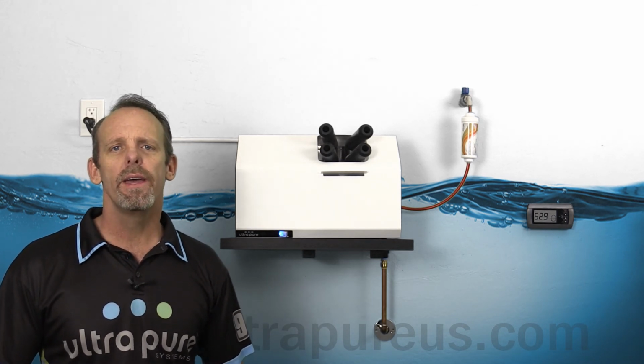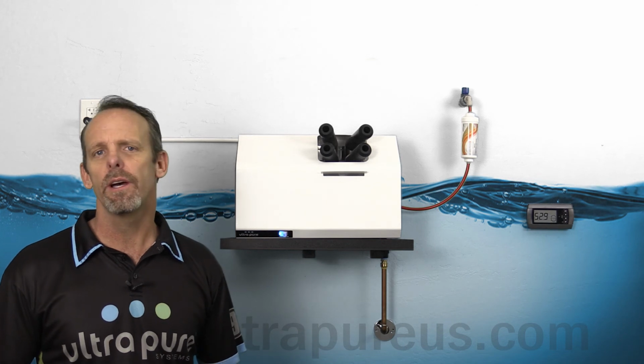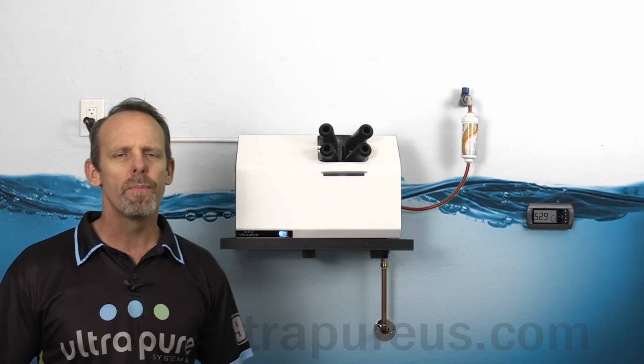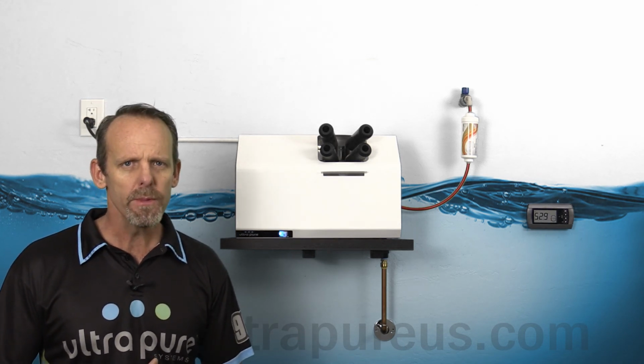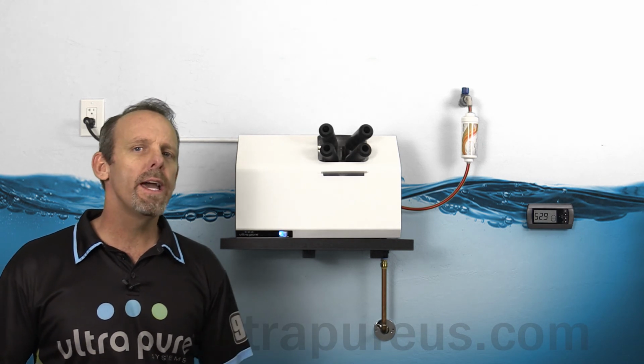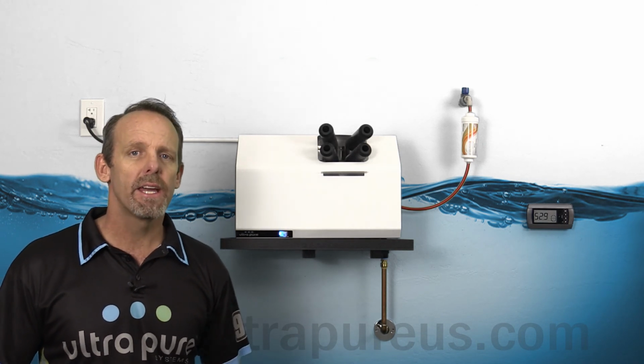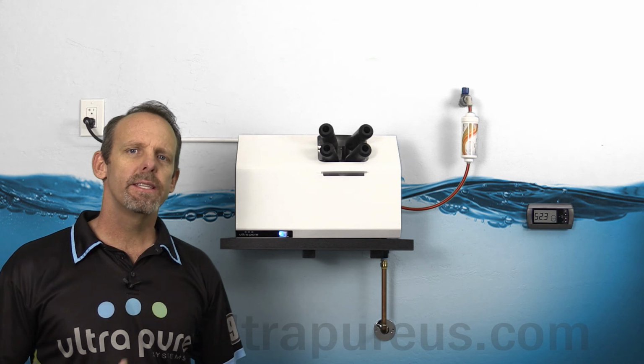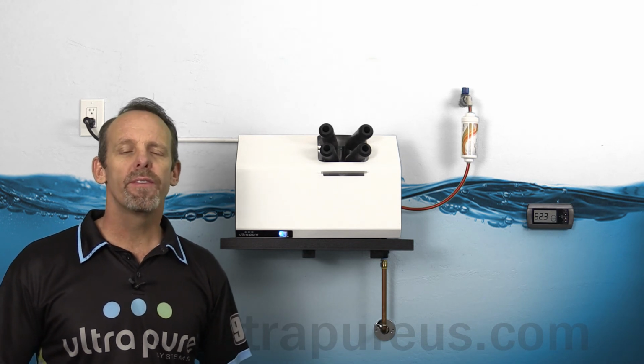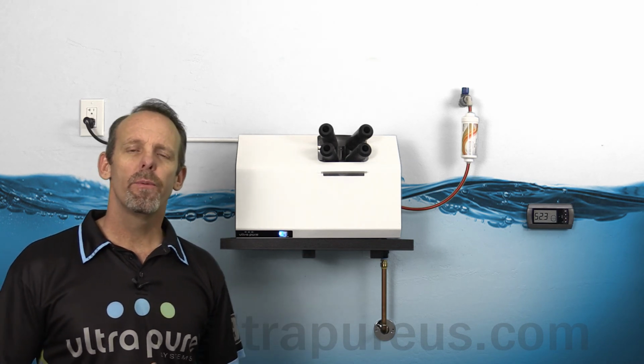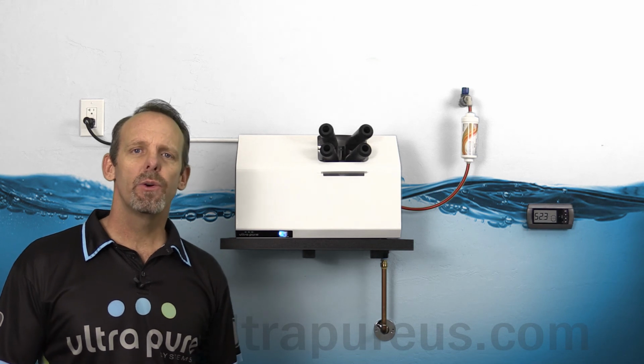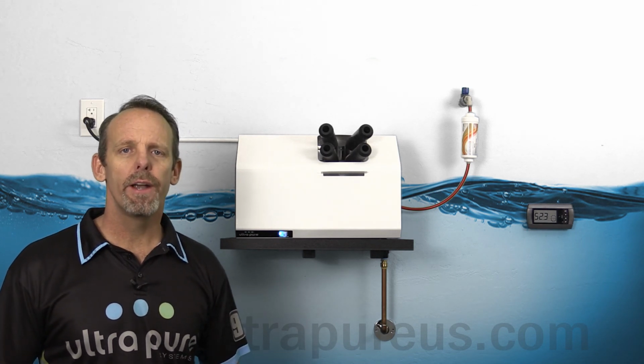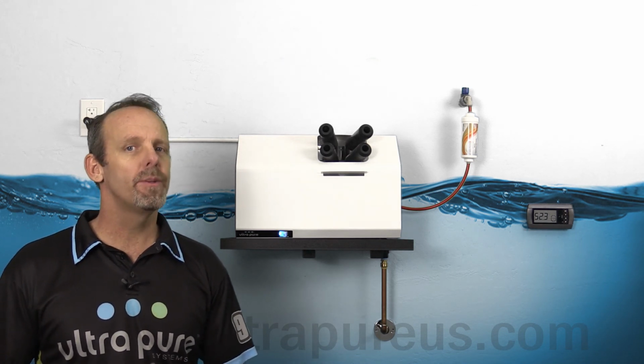We also have a switch. It's actually a current transmitter switch, very small, hooks up to our humidifier, and you run one leg of the humidifier fan through it, and when it senses current, it allows the humidifier to run. When the fan turns off, it loses current through that wire, and our humidifier won't be able to run.